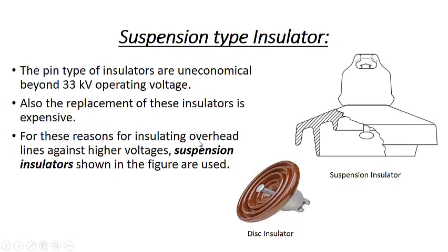For these reasons, for insulating overhead lines against higher voltages, suspension insulators are used. Usually it is a special name for the disc insulator, which is used when the transmission line is straight or the net force on the tower due to the transmission line is zero.